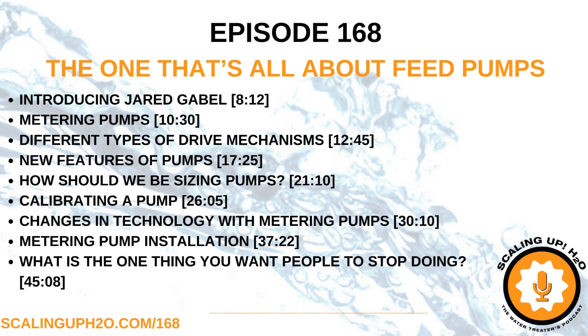But if you have a header on the suction side feeding multiple systems that both require that, that naturally would mean you would have to increase the size of that suction header so that you don't starve the two systems. And what can happen is the multiple pumps on the same header can start battling each other, because remember, they're reciprocating. They're going through a suction and discharge phase. And if one's going through a suction phase while the other pump's going through its discharge phase, that's a conflict. So you can either damage the pumps by ripping out the diaphragms, or something else can happen in the system so the feed rate will not be what you want it to be, and the process is not getting treated properly.